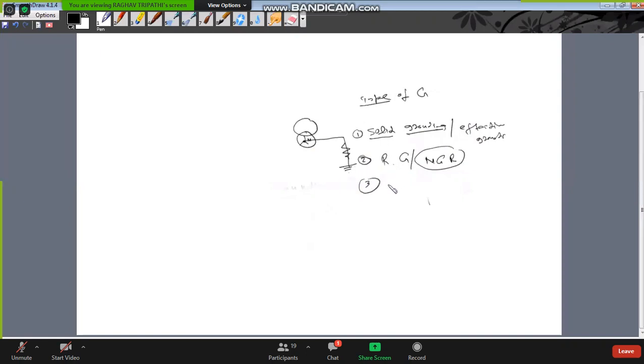The third method of grounding is zigzag earthing, or we select an earthing transformer. When we go with the earthing transformer... But sir, in our case we are using all three. Why? In your project in Afghanistan, you are using all three? Yes, sir.